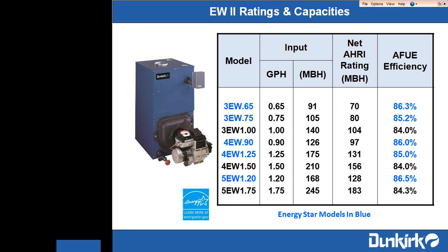Now, at the highest firing rate per section, which is how we ship them, you're going to get a minimum of 84% AFUE. We do make re-rate kits, which David has brought into stock, which will derate or downfire the boiler to a lower firing rate, which will also boost the AFUE as high as 86% on certain models, and that'll get us into Energy Star, anything 85% and above.